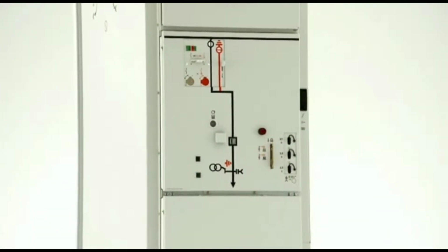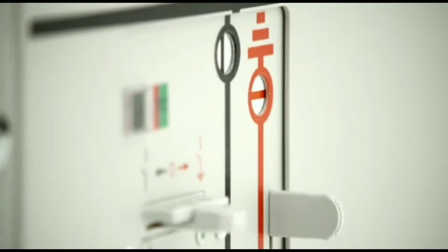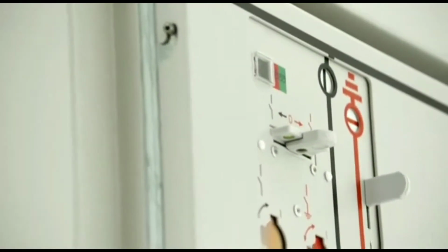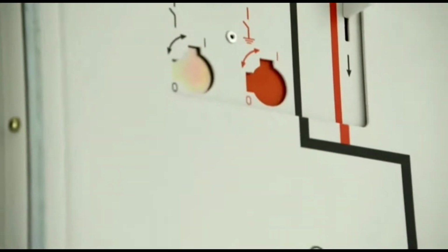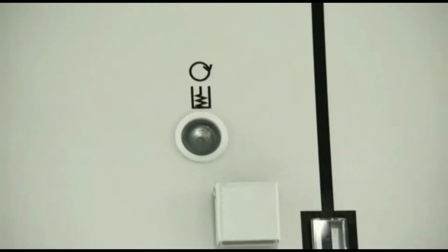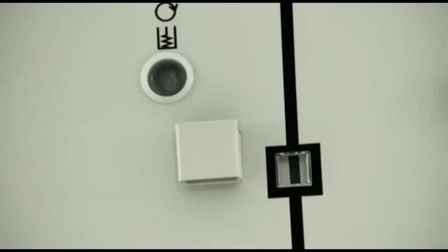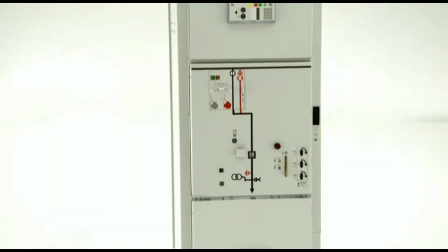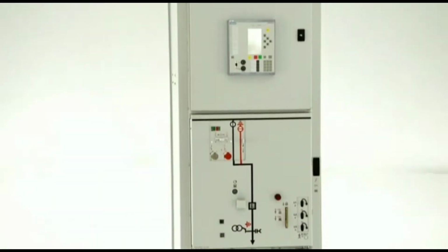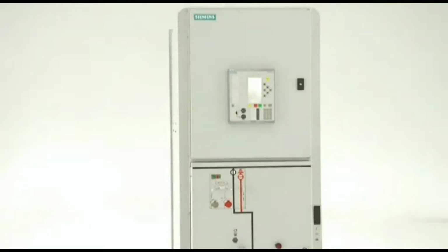Choose and execute means that the three-position disconnector can generally be operated only when the circuit breaker is in the open position. So, a choice is made regarding the planned switching operation, choose, which is then completed by closing the circuit breaker, execute. We'd like to show you this principle in more detail, using NX plus C as an example.